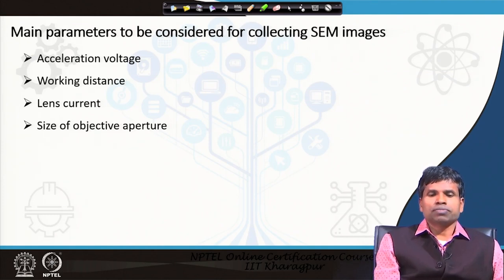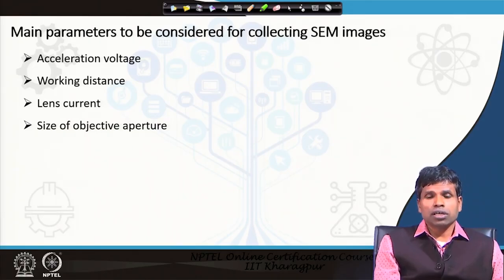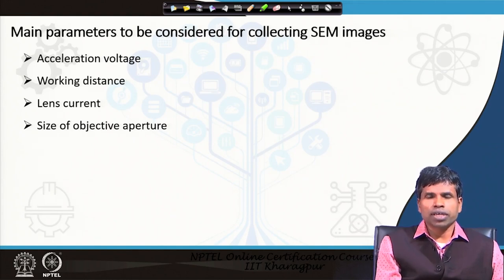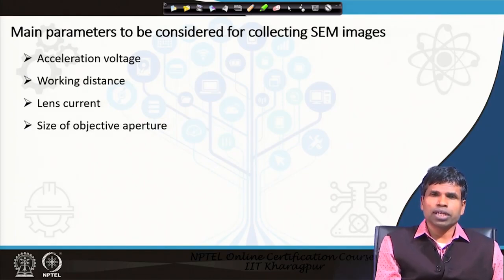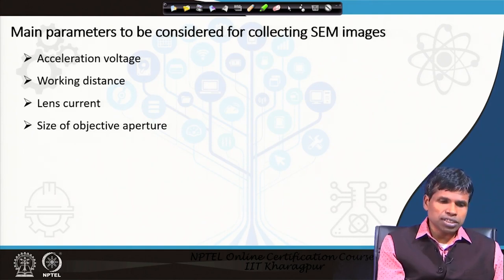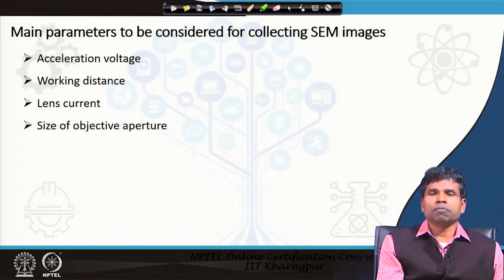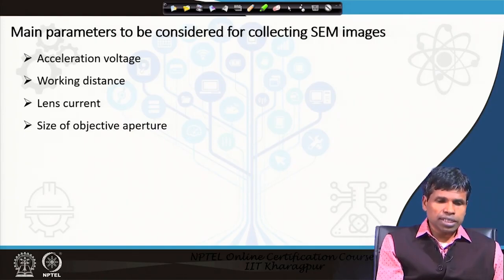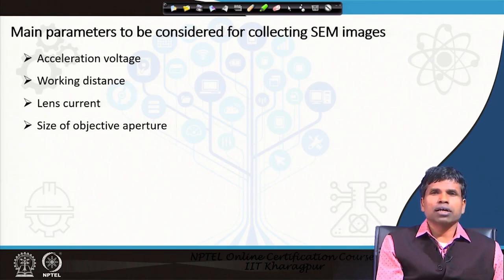Now, what are the main parameters that we must consider to collect a good SEM image? These are parameters under the control of the operator. When an operator goes to operate a microscope, he has certain control — he cannot control the sample, but he can change the parameters of the microscope to get the best image and the required information. The four main parameters the operator controls are: acceleration voltage, working distance, lens current, and size of the objective aperture.